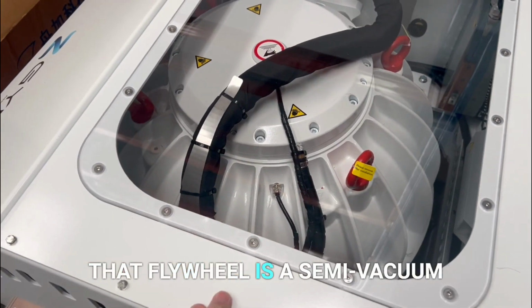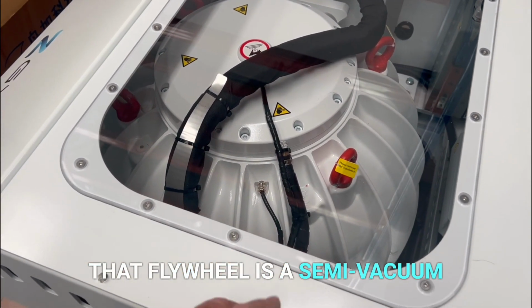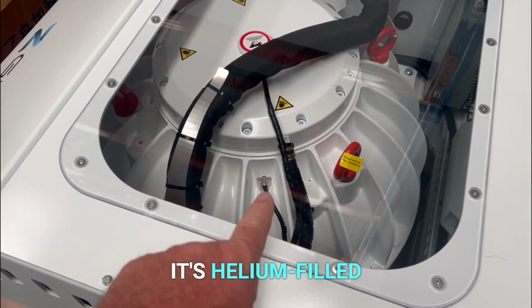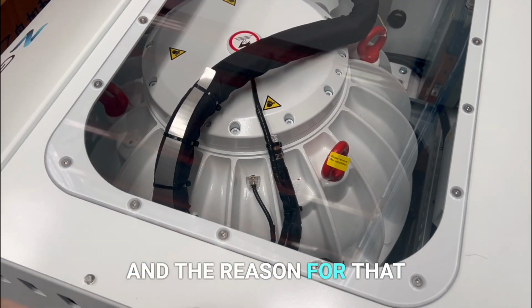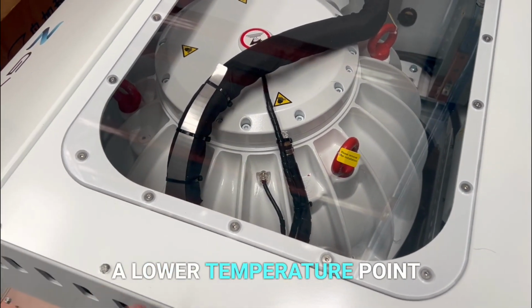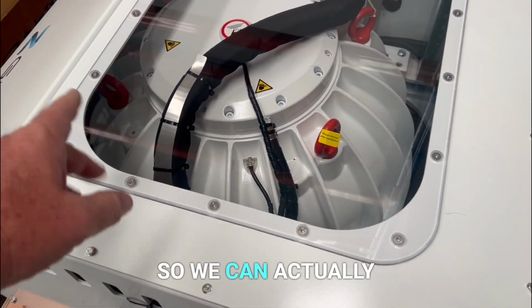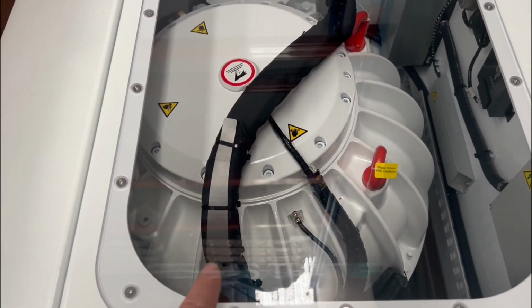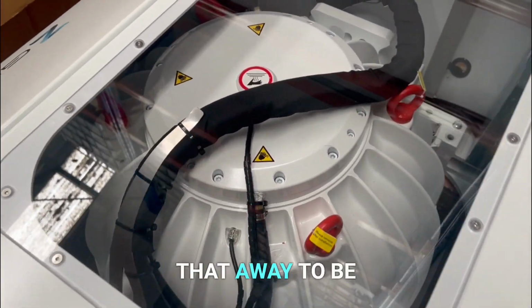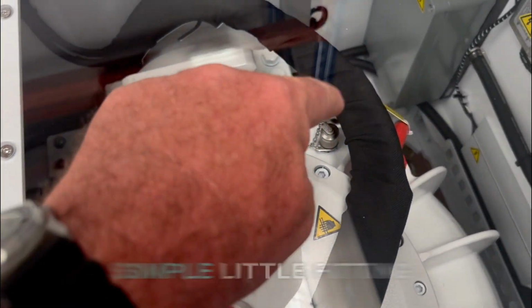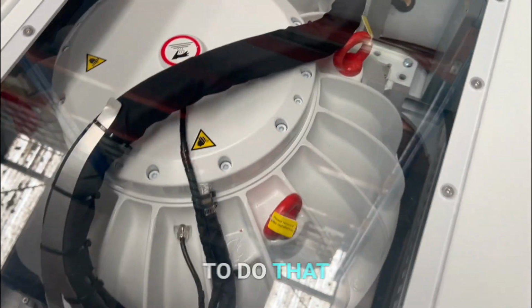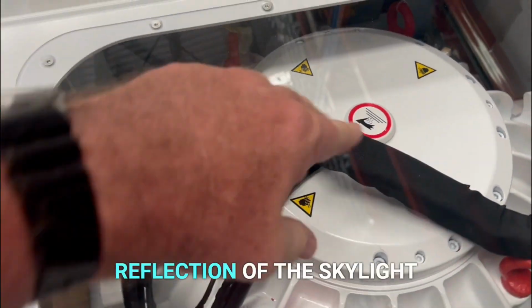That flywheel is semi-vacuum, not full vacuum, it's helium filled. The reason for that is helium has a lower temperature point, so we can actually regas that if we need to. We don't need to send that away to be done. There's a very simple little fitting there that allows us to do that, to actually create vacuum and push the helium in. It's a bit hard with that reflection of the skylight there, so I'll come back around here.